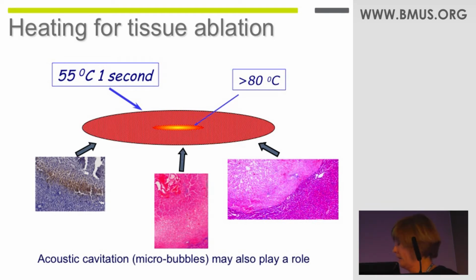The mechanism for cell killing is primarily heating. We know from thermal biology that if you reach 55 degrees centigrade and maintain it for a second, you get instantaneous cell death. So the extent of that white cigar-shaped lesion is determined by the contour at which you get that temperature or something equivalent. So 56 degrees for half a second or 54 degrees for 2 seconds. That equivalent, we call a thermal dose.